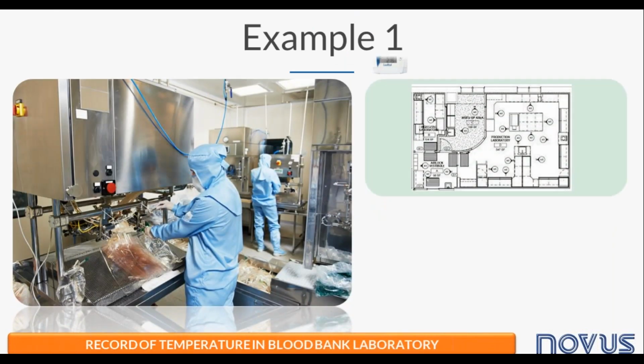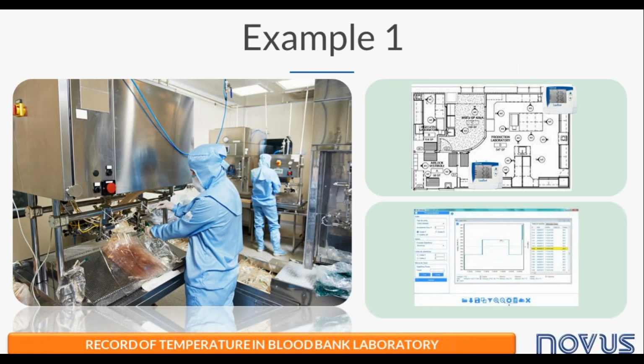So here we have an example of application, the recording of temperature in blood bank laboratory. Because the size of the facility is relatively small, an analysis of the laboratory blueprint may define 2 points of monitoring, mainly in critical locations. So, 2 logbox may be installed on those locations with configuration of high limit of temperature, triggering a buzzer alarm on its occurrence. The logbox may be fixed in the wall at eye level of a standing person. The data download may be done on daily basis for getting history profile of temperature for future audits.